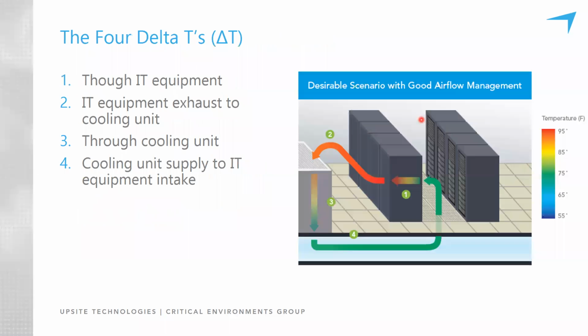So I want to share one more concept with you, which is the 4 delta T's. Most people are aware of 2 of the delta T's in a computer room. On this image, they're labeled as 1 and 3. Obviously, we all know that air warms up as it flows through IT equipment, and we know that air cools down as it flows through cooling units. There are 2 more delta T's that are very important to measure, and they can really provide some insight as to the potential for optimizing the conditions in the room. And that's labeled as 2 and 4 on this image.